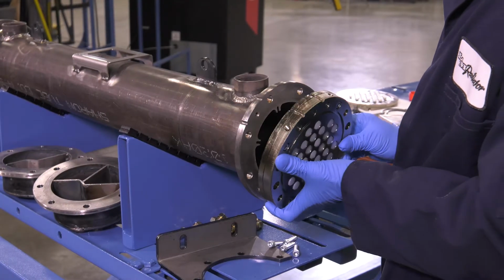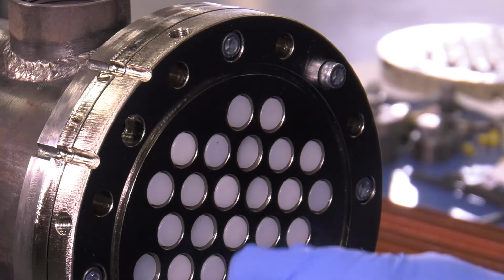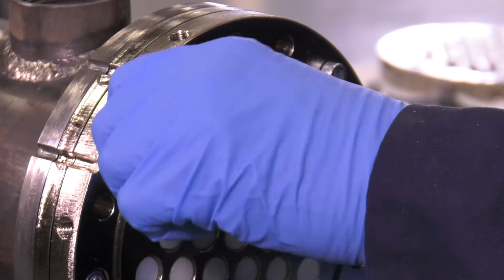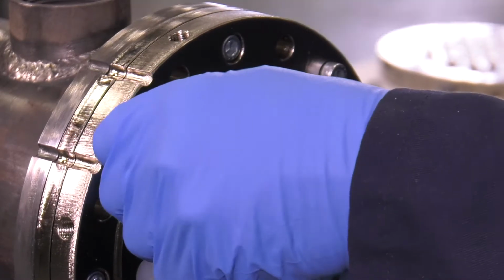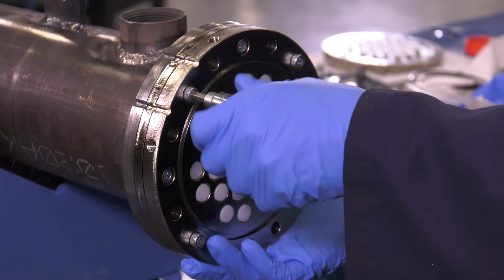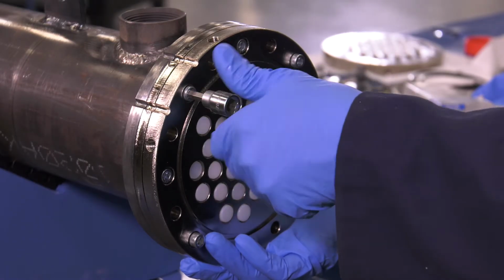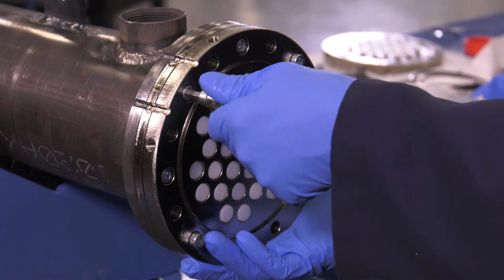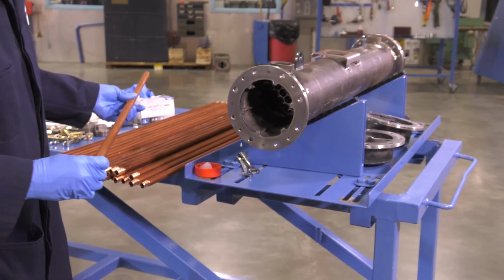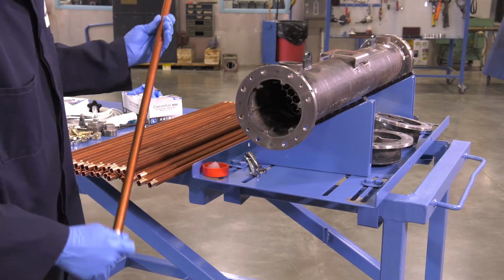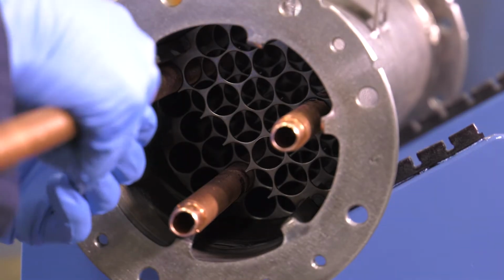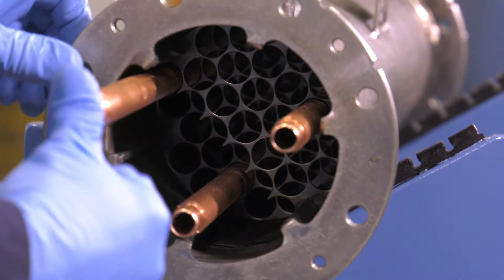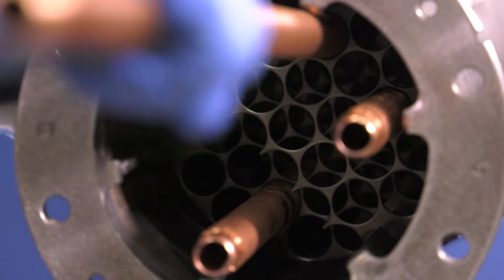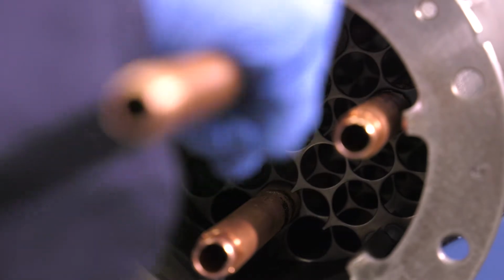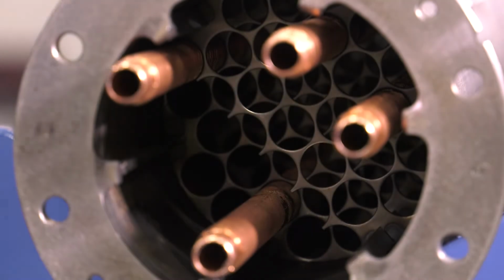Install one header plate to end of the cooler. Note the orientation notches on the header plate and the shell flange. Ensure they are lined up. Install the header retainer bolts. Leave loose until all tube ends are pushed into the header plates. Apply a light coat of assembly lube to the clean tube ends. From the opened end of the cooler, install 4 tubes through the baffle assembly and into the attached header plate at 3, 6, 9, and 12 o'clock positions to maintain baffle to header alignment.